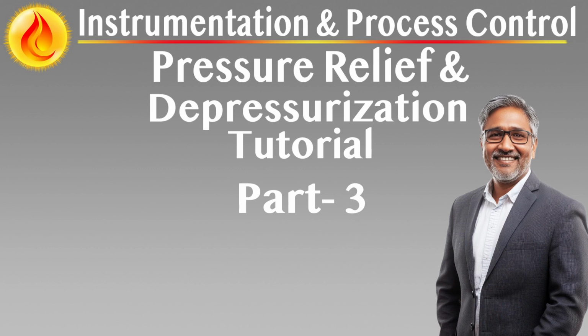The system must be capable of reducing pressure to 50% of the equipment's design pressure within 15 minutes during fire exposure. This 15-minute window does not imply depressurization ends after that period. Rather, it represents the required rate for initial pressure reduction.